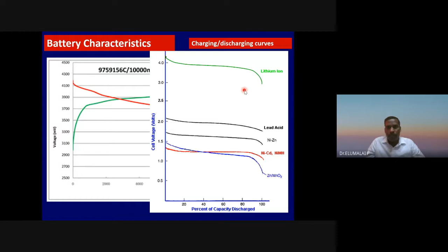Relatively, compared to lead-acid batteries, lithium-ion batteries can have higher efficiency. Compared to all other batteries, nickel metal hydride and nickel cadmium batteries can give a very high constant voltage. What is this constant voltage? We named it the plateau region. There is no plateau in supercapacitors, but there is a long plateau in batteries. That is an advantage for batteries and a disadvantage for supercapacitors. It is always sloping, it's dynamic. The power delivery of a supercapacitor is dynamic, not constant, whereas in batteries it is constant, at least in this duration. Highly constant, highly reliable. And supercapacitors are dynamic, sloping. At each second, each minute, there is a change in the slope.